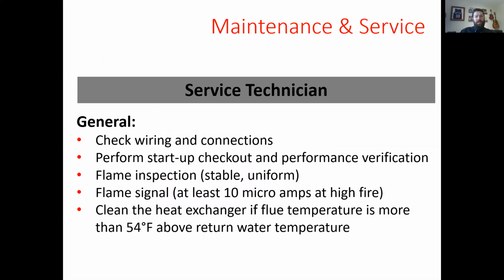All right, let me go over a few maintenance notes here. Generally speaking, this is what your service technician is going to do when you have an issue after checking out your error code, obviously. Most of the time, you're going to check your wiring, perform your startup performance verification, and inspect the flame. Is it stable? And check your flame signal. If you have an issue, you're going to clean the heat exchanger if the flue temperature is more than 54 degrees above the return water temperature.